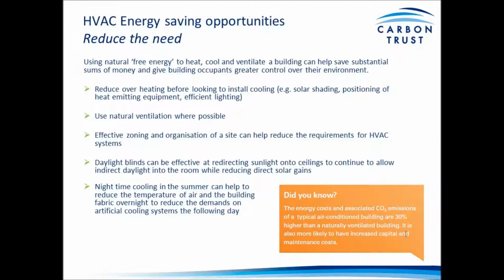An interesting fact in the orange box there is that if you're looking to go from a standard heating and natural ventilation system within your office to a fully air-conditioned office, it's likely to cost in the region of 30% more to run. Now, this is a rule of thumb guidance. It's very much dependent on the systems you have. But typically, even though air conditioning systems can be very efficient and effective, you will be using them more than likely during the summer to provide cooling, whereas you wouldn't necessarily with a standard heating system and natural ventilation system. Hence the higher general overall costs to run them.